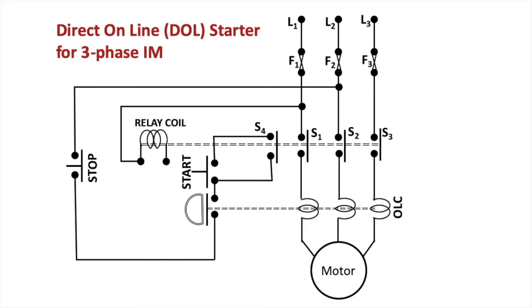Now after that, you see the three switches S1, S2, S3, which are connected directly to the motor through the OLC, which is a thermal relay, and S1, S2, S3 are the switches giving the supply to the motor. S1, S2, S3 are directly connected to S4, which in turn is connected in parallel to the start position. The start button is normally open. When you push it, it will be closed, and therefore S4 will also be closed, closing the remaining three switches which connect the line to the motor.